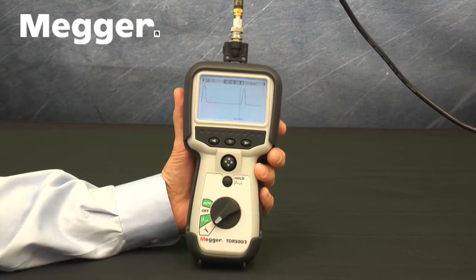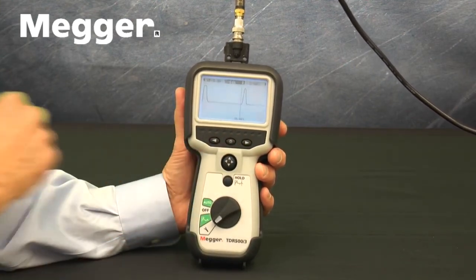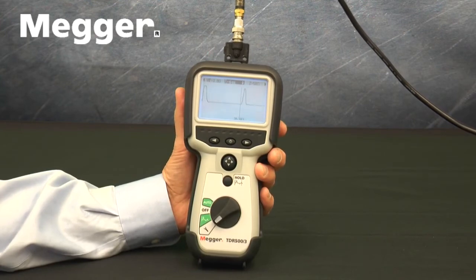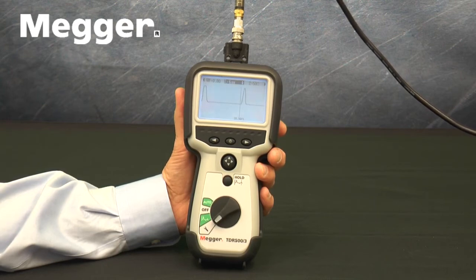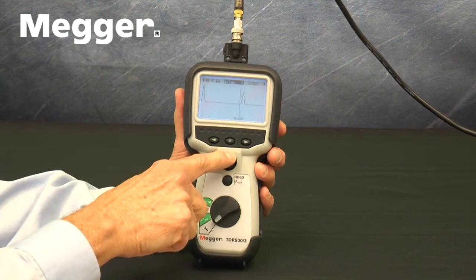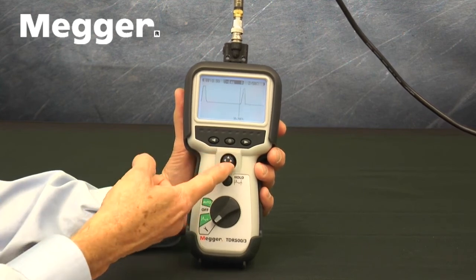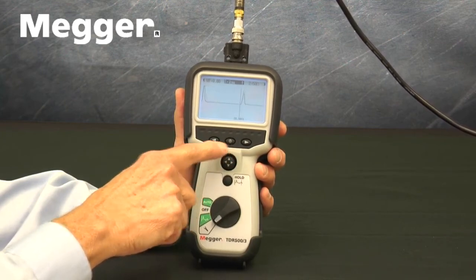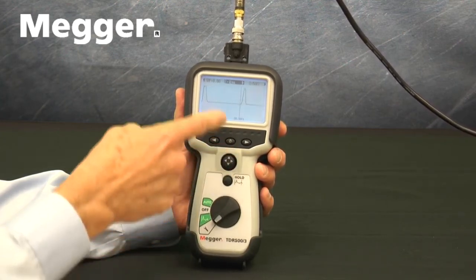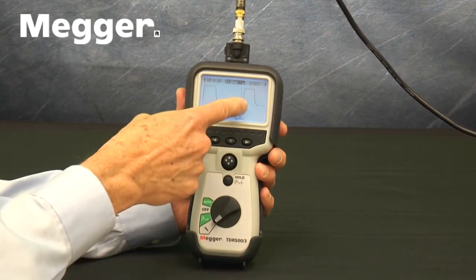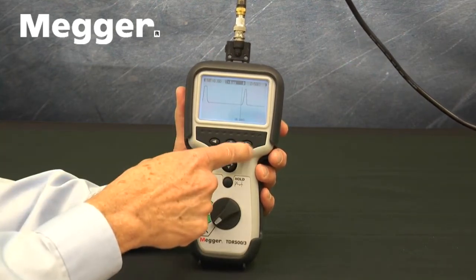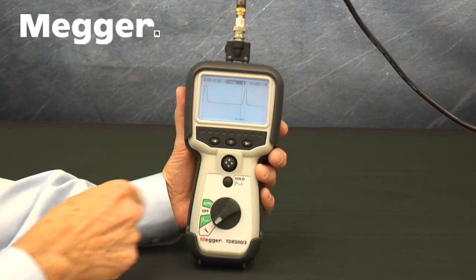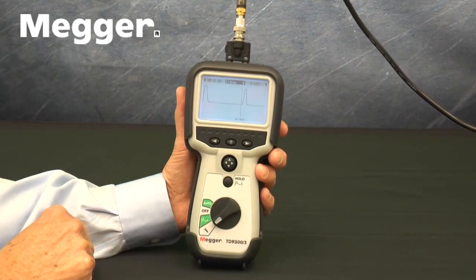From there, push the right arrow to show the pulse width icon, which, while representing a pulse, looks like a top hat. The TDR500 tries to get the best results for display. This setting lets the user override the TDR500's automatic selection of pulse width. There are 3 pulse widths available: 2 nanoseconds, 6 nanoseconds, and 20 nanoseconds. Bump the joystick up or down to change the pulse width setting and override the TDR500's choice.